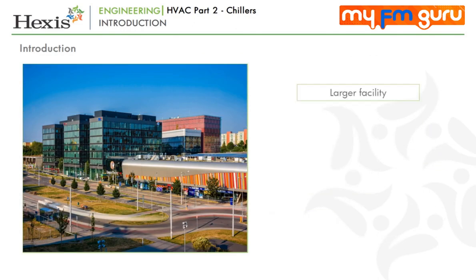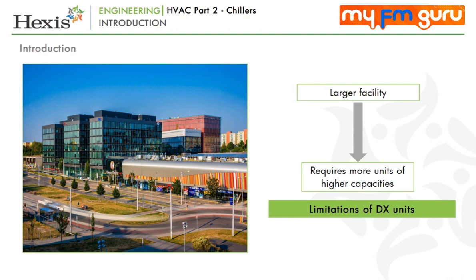Now consider a slightly larger facility to be cooled, for example an auditorium or a floor comprising multiple offices. In such a case, we will have to install more units of higher capacities to cool the larger area. DX units have a limitation on the length of piping that can be used due to issues of pressure drop and thermal losses. Hence, we cannot have one unit serving too many or faraway indoor units. Also, the amount of refrigerant used increases with the number of units or long piping.